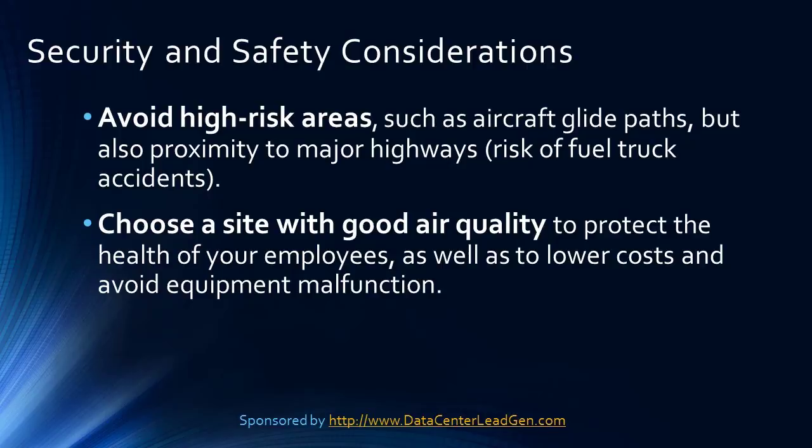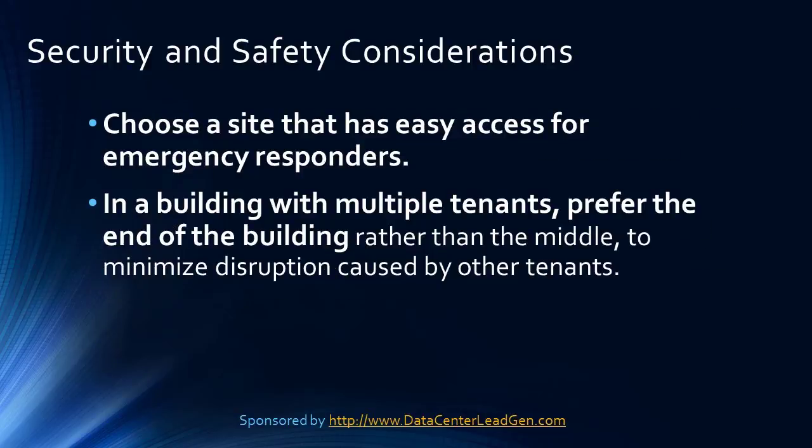Security and Safety Considerations: Security and safety are typically the highest priority in data center site selection. Avoid high-risk areas such as aircraft glide paths, but also proximity to major highways due to the risk of fuel truck accidents. Choose a site that has easy access for emergency responders and good air quality to protect the health of your employees, lower costs, and avoid equipment malfunction. In a building with multiple tenants, prefer the end of the building rather than the middle to minimize disruption caused by other tenants.